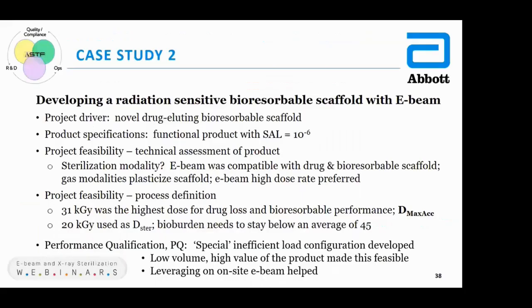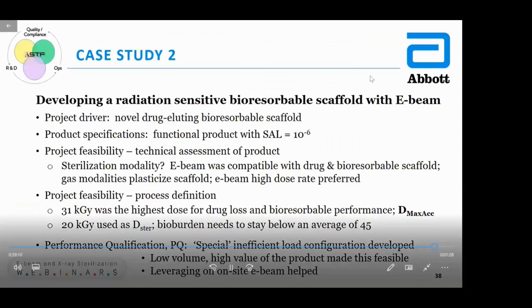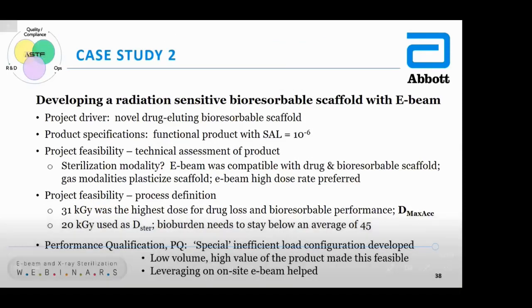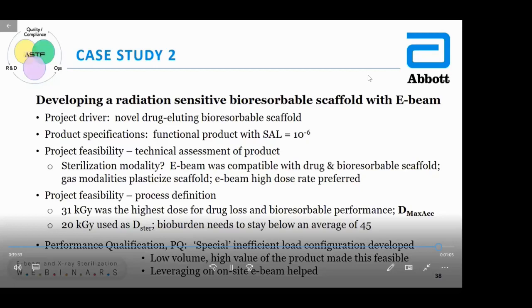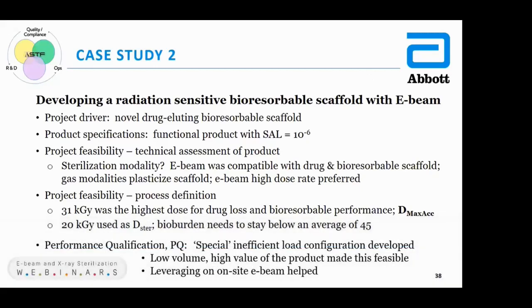And so the key last point here in the case studies is that for the performance qualification, the PQ, we needed a special, efficient, not inefficient, efficient load configuration developed. This can go both ways. It had to be efficient in terms of getting low DUR, but it ended up being relatively inefficient in terms of throughput.